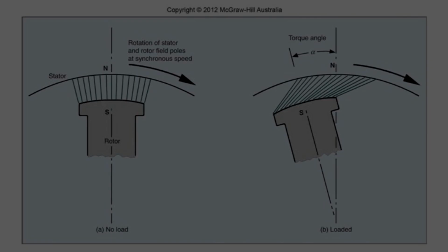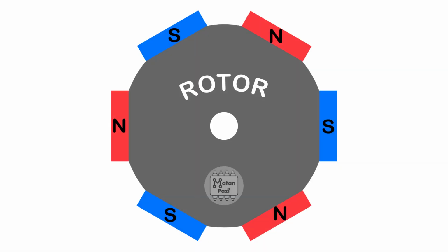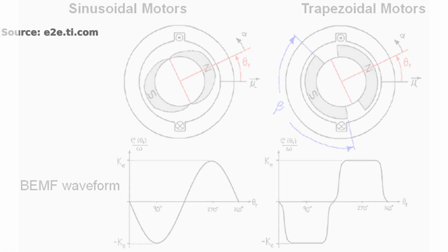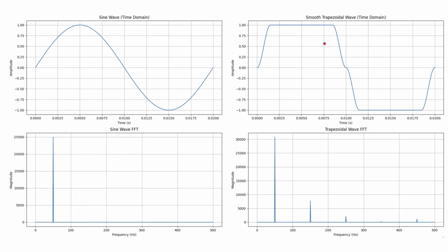field in the stator. A simple rectangular magnet is cheapest to manufacture and assemble, but its magnetic flux is relatively constant across its width. And with a small gap followed by a magnet with the same shape and opposite polarity, we get a relatively trapezoidal back EMF waveform. And if we compare the FFT results of a sine wave and the trapezoid, we can see the harmonics in the trapezoid. Also notice that the trapezoid has more energy in the fundamental frequency compared to the sine wave. So just keep in mind that although harmonics are added, a trapezoidal waveform can offer a higher overall flux.